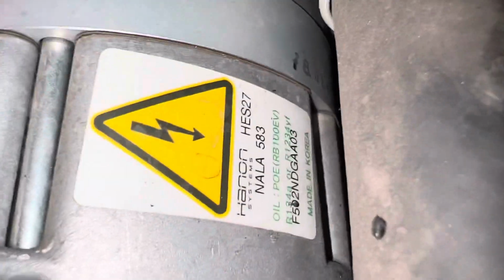Now let's try to find the compressor down here. Take a look at the electric compressor. See if I could zero in on any labels for you guys. Let's get up there a little closer. Come on. Can we see a model number? Sorry guys, this is going to be bad because it's not easy to access. There we go. You guys can see those model numbers. I don't know if you can see it. The screen lens is almost out of my sight from my eyes. Alright, so that's the electric compressor. Here's the suction line. And the discharge, and there's only one. This is not a heat pump. Or at least, yeah, this is not a heat pump.